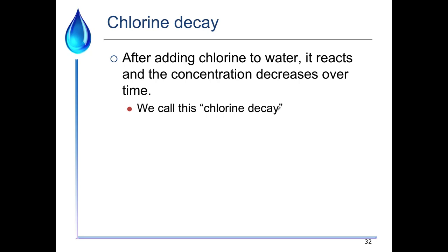Chlorine also decays over longer time scales — what we call chlorine decay. After the initial fast reactions, concentration decreases over time due to reactions with pipe walls, long-term reactions with organic matter in solution, and possibly temperature effects. Chlorine is a reactive substance and will react away over time.